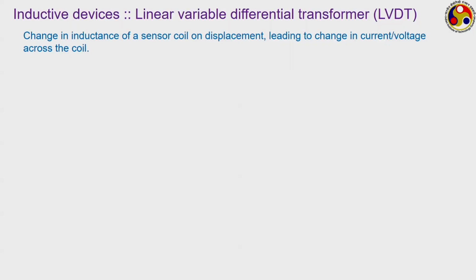The next devices we have in line are inductive devices. Like in the previous case, we made use of the change in resistance to measure displacement. Here we are going to make use of the change in inductance in some inductive coil to measure displacement. The device we are going to talk about is known as LVDT, or linear variable differential transformer, an extremely common method of displacement measurement that can operate over a very wide range of distance values, and is a common measurement device in some very critical application areas.